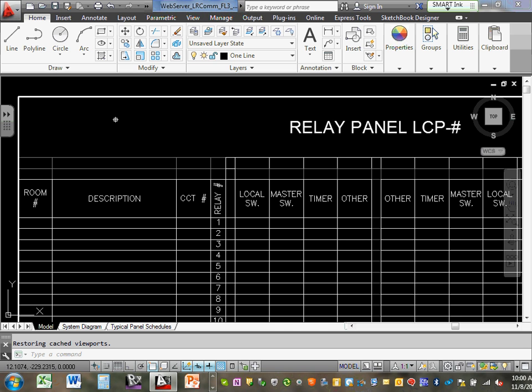A lot of guys are building this as they're building their lighting panel schedule, right? So they've got LP1 here, and they know that LP1 circuit 1 is going to feed these four rooms. They go right to the relay panel schedule and ask, since I'm on circuit 1, how am I going to break circuit 1 down? I'm going to take that to the relay panel and break it down right now while I'm doing it. And you guys will be doing that. For the project that we did, there's a schedule we already got from you a long time ago. Slightly different, similar, but different. You will be assigning a circuit to a location, to a relay, to a switch. Exactly the same thing. It's coming in two weeks.